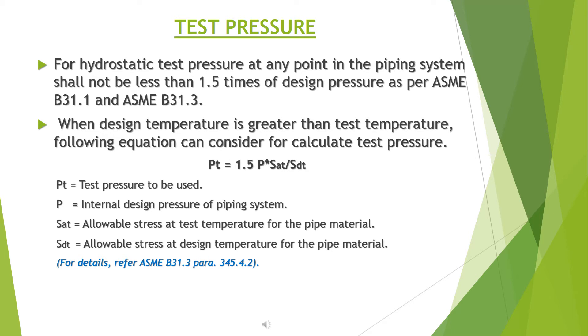For hydrostatic testing, the test pressure at any point in the piping system shall not be less than 1.5 times the design pressure, as per ASME B31.1 and ASME B31.3. When design temperature is greater than test temperature, the following equation shall be used: PT = 1.5 × P × (SAT / Sdt), where PT is test pressure, P is internal design pressure, SAT is allowable stress at test temperature, and Sdt is allowable stress at design temperature. For details, refer to ASME B31.3 para 345.4.2.